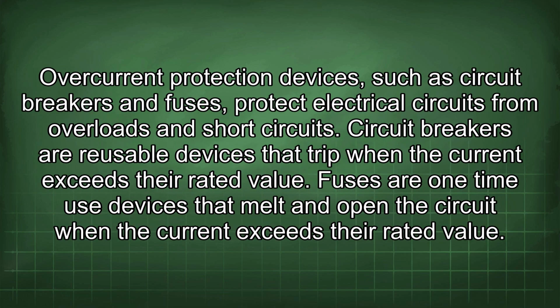Overcurrent protection devices, such as circuit breakers and fuses, protect electrical circuits from overloads and short circuits. Circuit breakers are reusable devices that trip when the current exceeds their rated value. Fuses are one-time use devices that melt and open the circuit when the current exceeds their rated value.